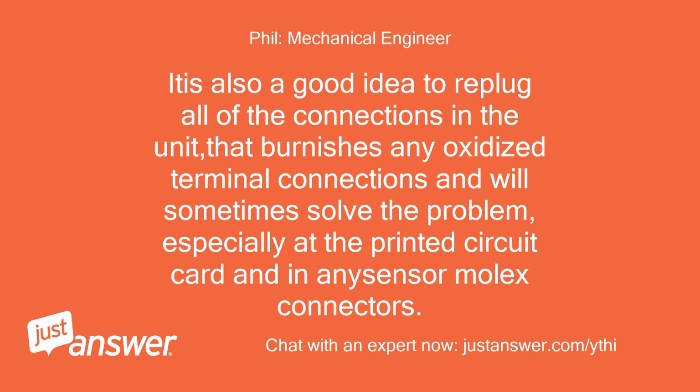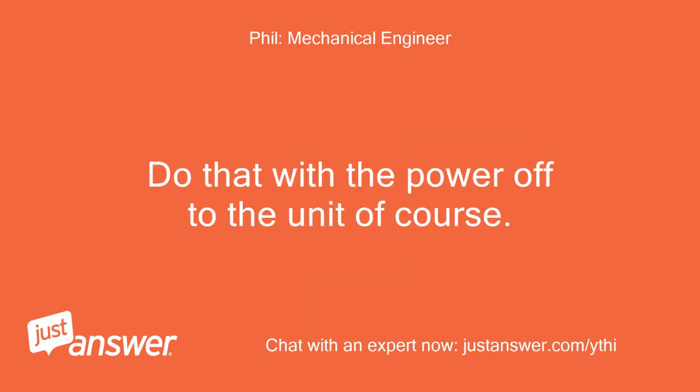It is also a good idea to replug all of the connections in the unit. That burnishes any oxidized terminal connections and will sometimes solve the problem, especially at the printed circuit card and in any sensor Molex connectors. Do that with the power off to the unit, of course.